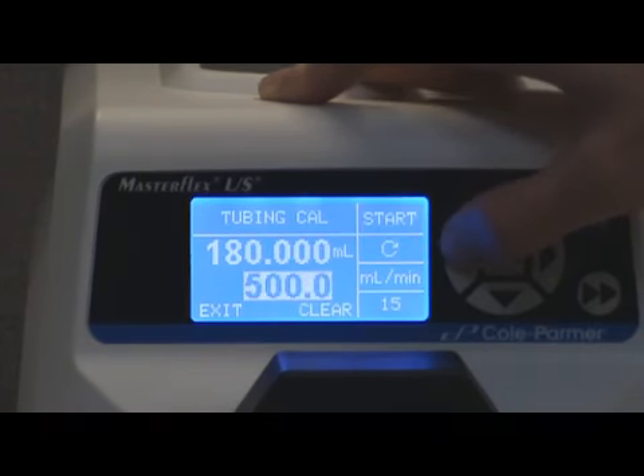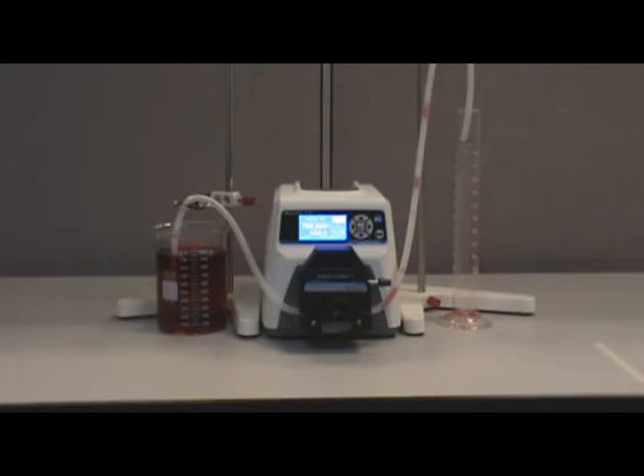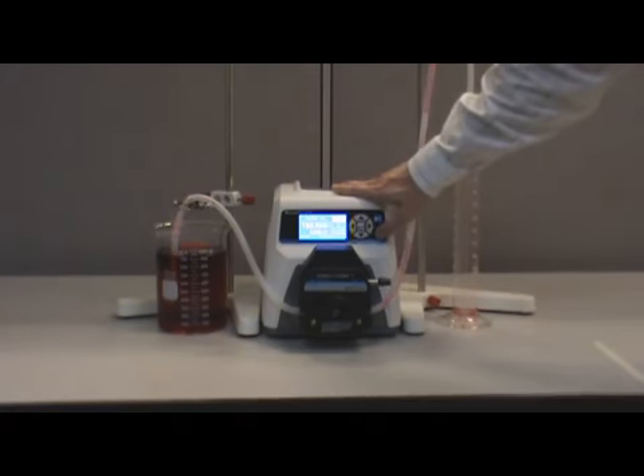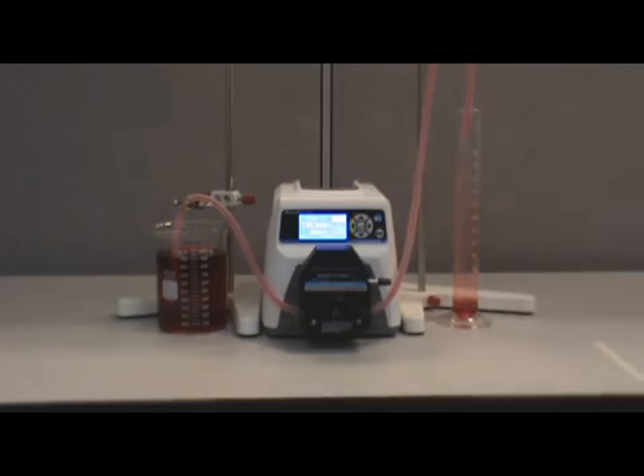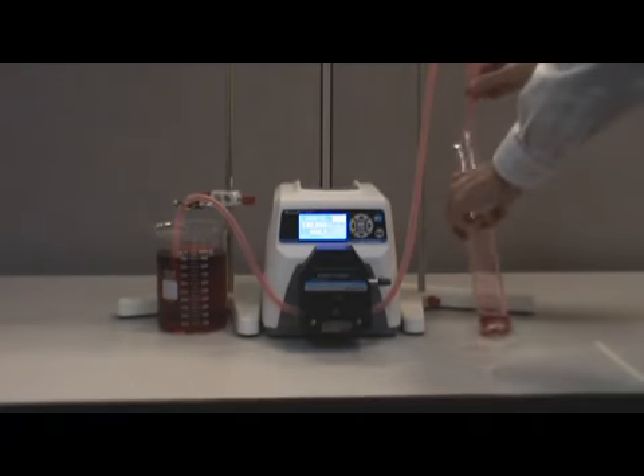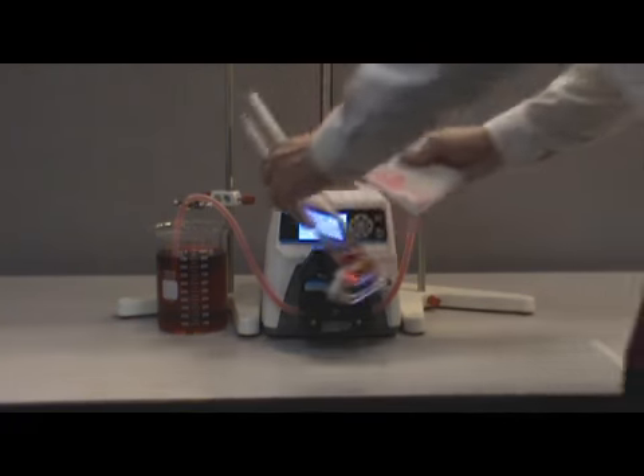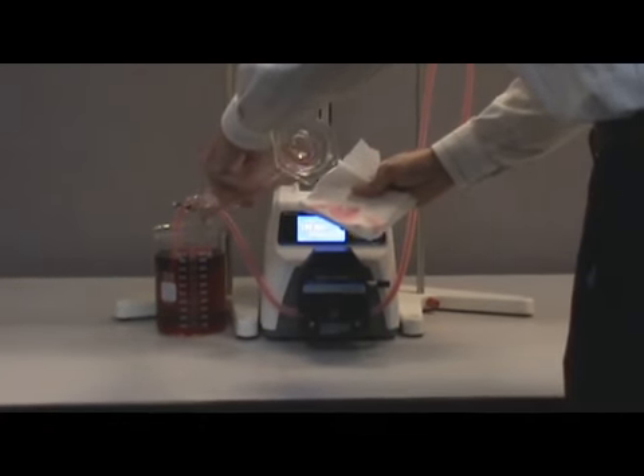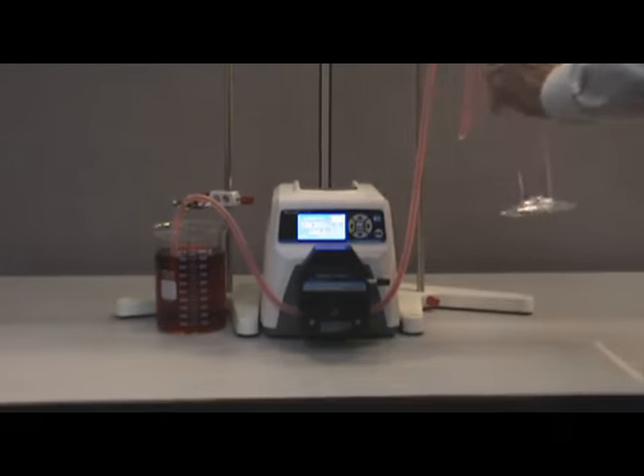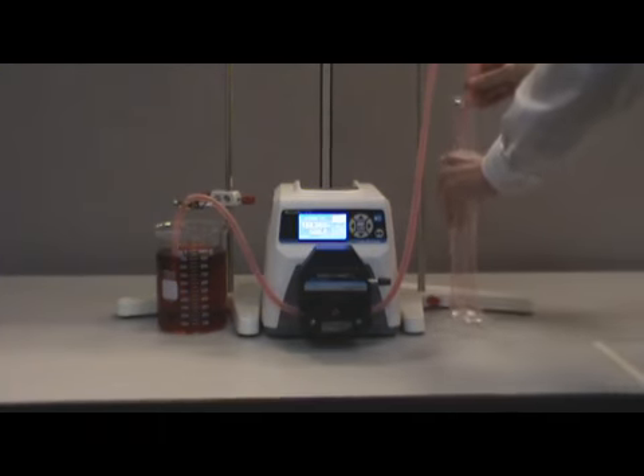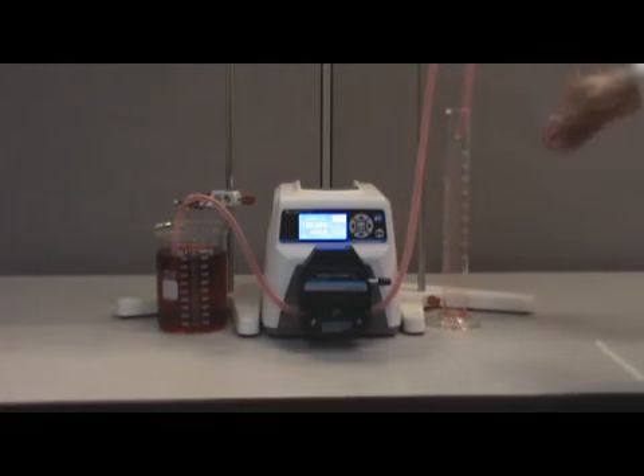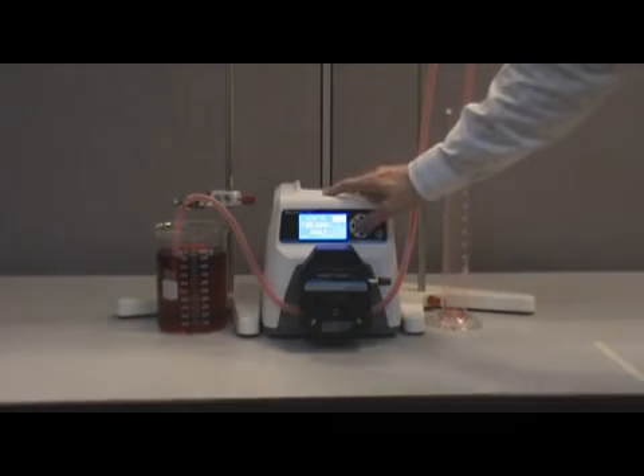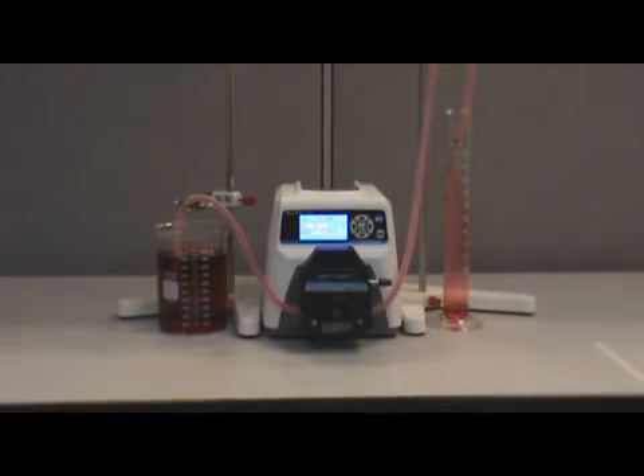The calibration volume is fixed and cannot be changed. Press and hold the prime key to prime the pump and fill the tubing with water. Water in the graduated cylinder should be emptied back into the beaker to ensure an accurate measurement during the calibration process. Once this is done, highlight the start field and press the enter key to begin the calibration.